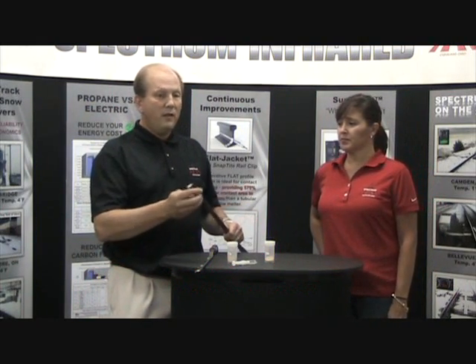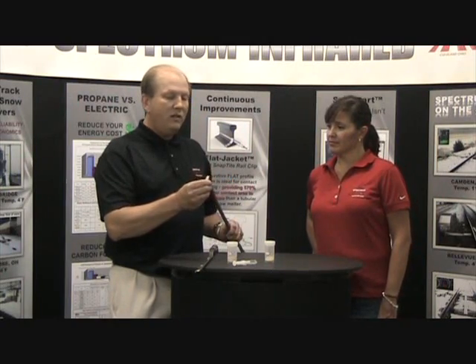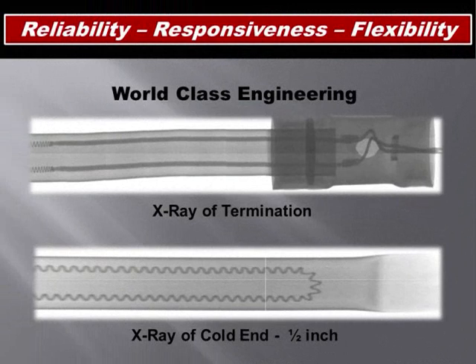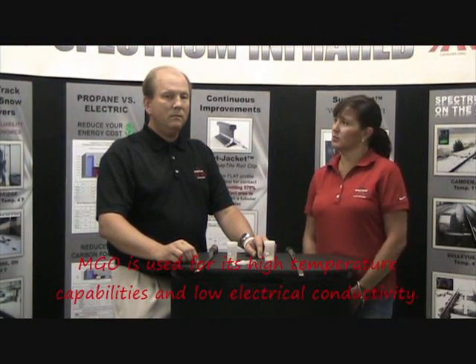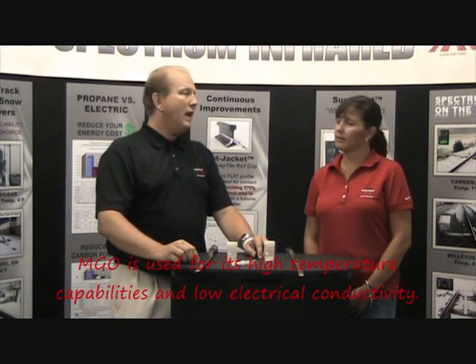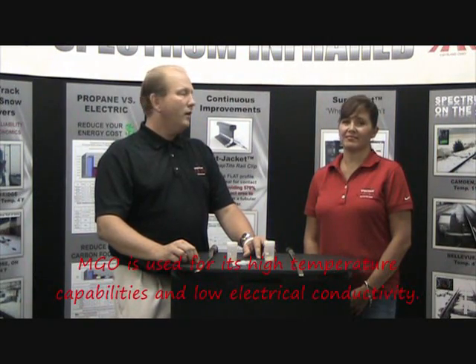A snowmelter is typically a nichrome wire encased in magnesium oxide, sheathed in either stainless steel or Incoloy. This x-ray shows the nichrome wire inside the sheath. Magnesium oxide is used in the heating element because of its high temperature capabilities and its low electrical conductivity.